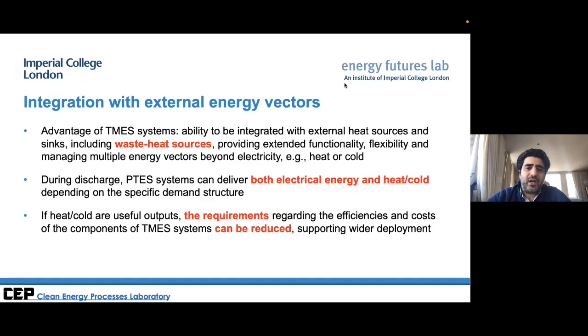An important advantage of thermomechanical energy storage is that the technologies have embedded flows of heat and cold as part of their operation, meaning they can integrate with external heat sources. This can significantly affect the economics. If thermomechanical energy storage is co-located with an industrial plant or other end user that has demand for heat or cold, or has waste heat or cold, the preference for this type of technology becomes even greater.